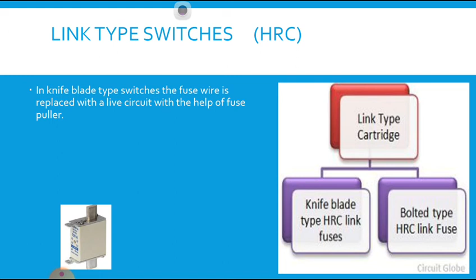This is known as the knife type, at both ends it has leads. You can see the knife. So in knife blade type switches, the fuse wire is replaced on a live circuit with the help of a fuse puller. By using the fuse puller, we can directly pull it from the base. The operation is the same, but the terminal is different, and we can easily replace it whenever we require by using the fuse puller. Just like a bearing puller, we have the fuse puller also. By using this, we can remove it even under the condition, and the possible arc may be nullified by the powder inside.